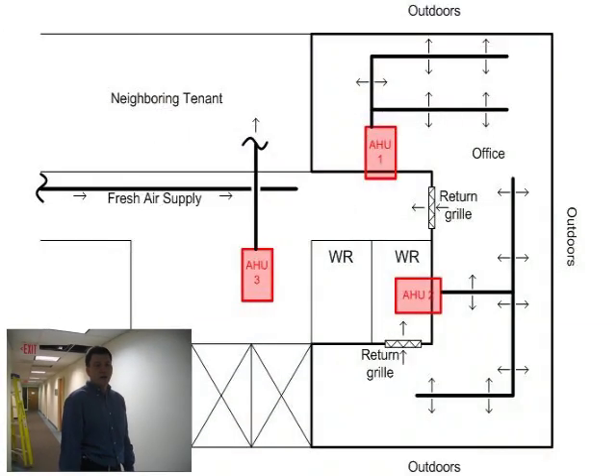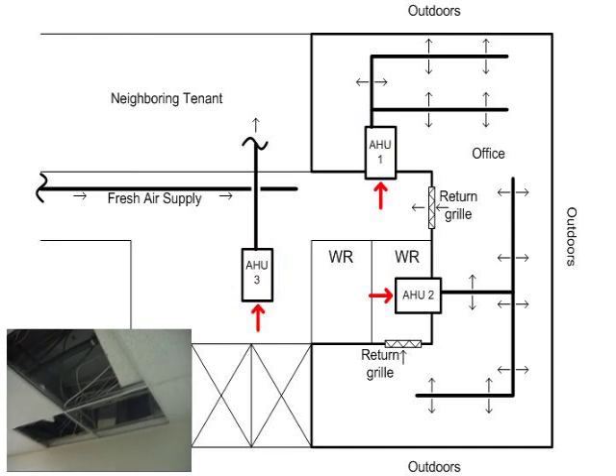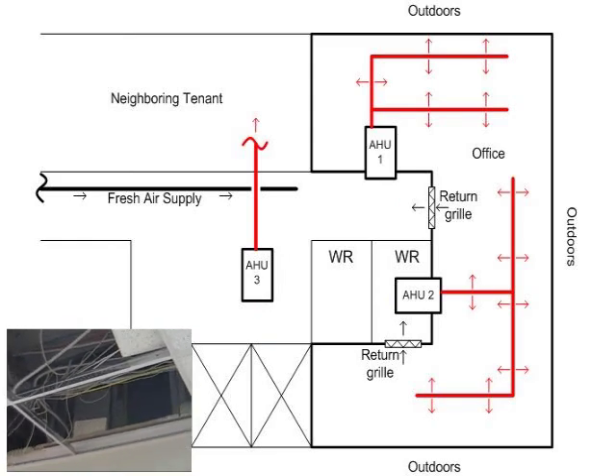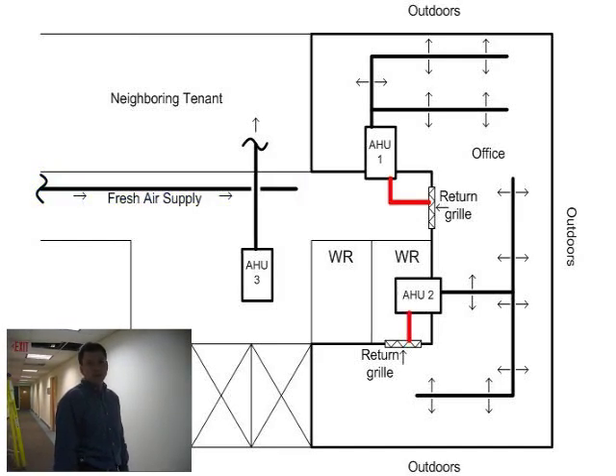What we found here is that there are three air handlers in this area, all serving spaces with supply air that are not connected back on the return side. The returns are all out in the hallway area and the supplies are in the work spaces, separate from the hallway. So they're making a lot of noise but not moving a lot of air. The outside air is just ducted into the overhead return space and not hard-ducted to any of these returns. The bottom line is that the return air has to be hard-ducted to the space that the air handler is actually supplying air to.